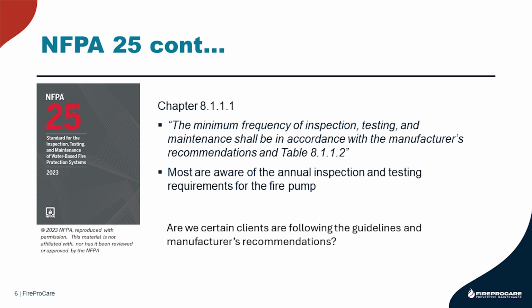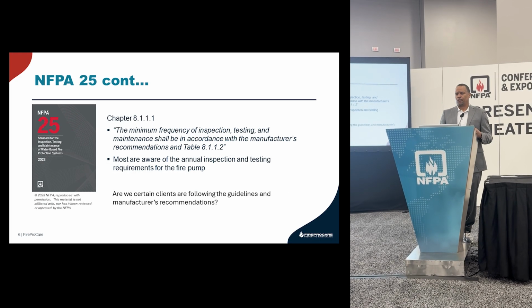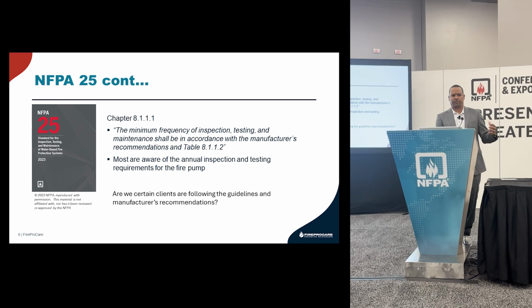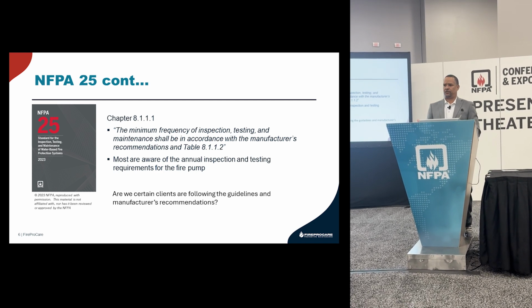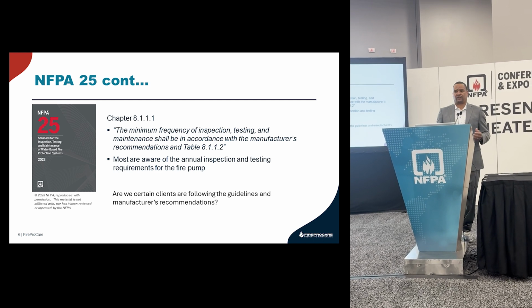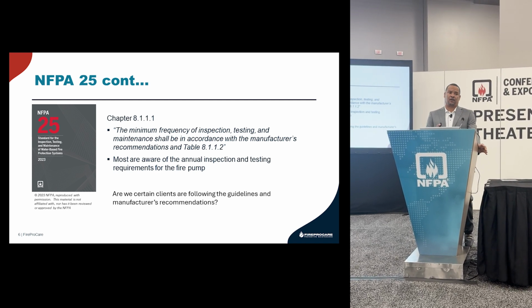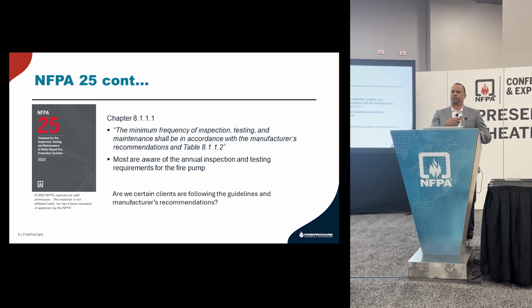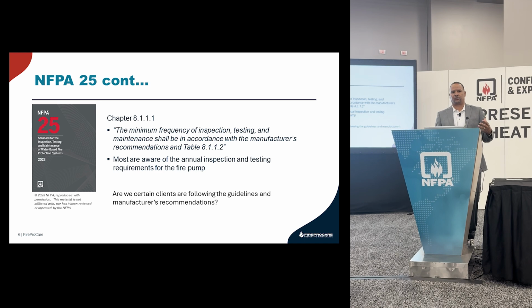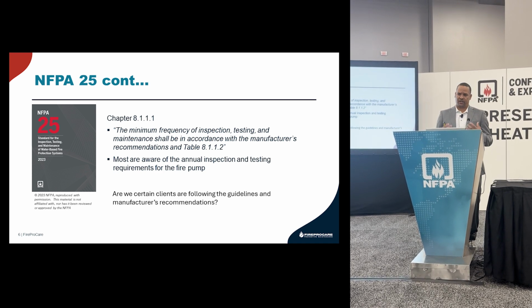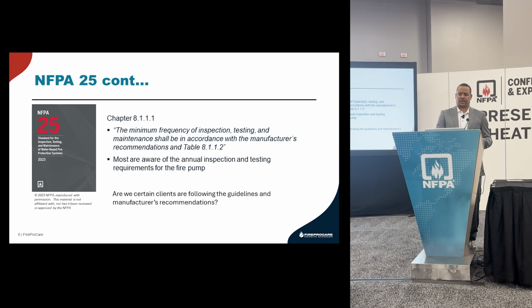Table 8.1.1.2 in NFPA 25 specifically says you need to work with the manufacturer regarding this table. Are we certain our clients and customers are following NFPA 25? It is a standard, and UL and FM will list and approve controllers and other parts of this system based on whether you meet this standard.